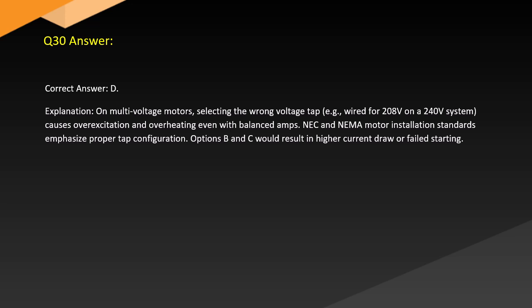Answer. Correct answer: D. Explanation. On multi-voltage motors, selecting the wrong voltage tap, e.g. wired for 208 V on a 240 V system, causes overexcitation and overheating even with balanced amps. NEC and NEMA motor installation standards emphasize proper tap configuration. Options B and C would result in higher current draw or fail at starting.